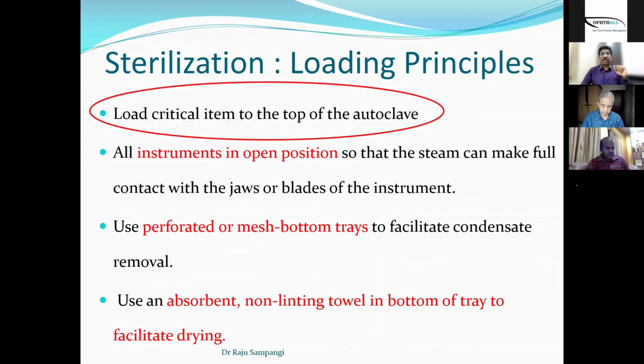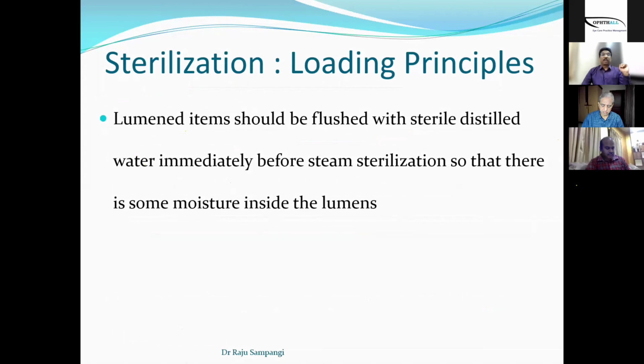And it's again important to understand that we should load the critical items. Suppose you want to use your phaco handpiece, this should be loaded at the top of your autoclave, because the bottom of your autoclave is the most likely place where the sterilization can fail, while the top of the autoclave is the place where the steam starts from. So you should load your most critical item at the top of your autoclave. Then, coming to lumen items, they should be flushed with distilled water immediately before the sterilization, so that some amount of moisture is left inside the lumens. This will heat up and will sterilize the lumens from inside also. That's what has been suggested.